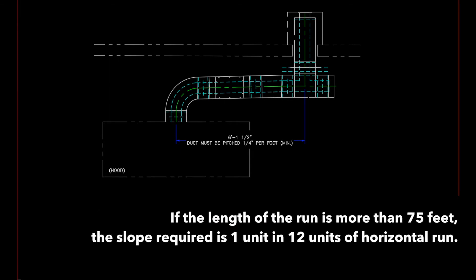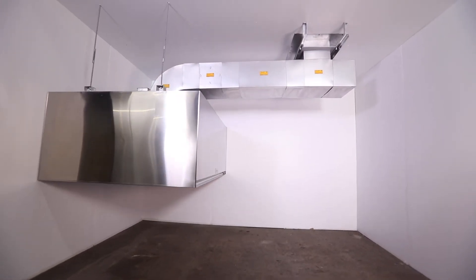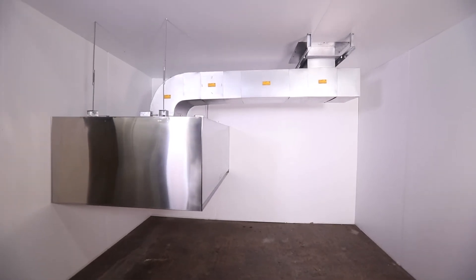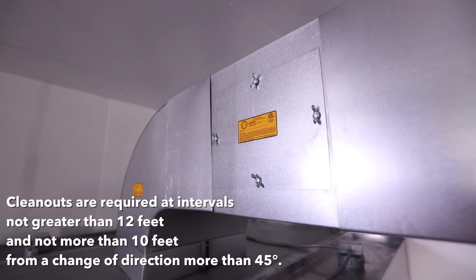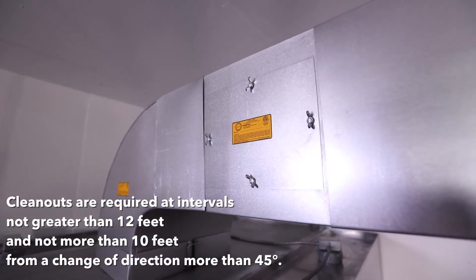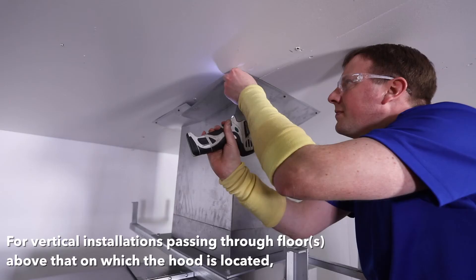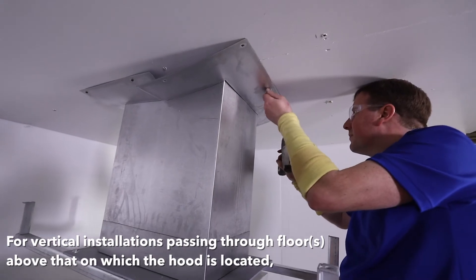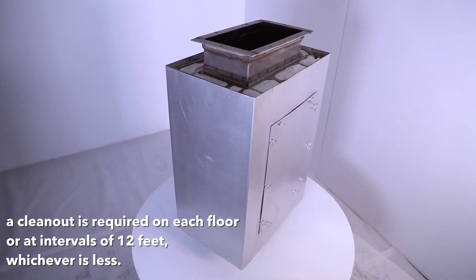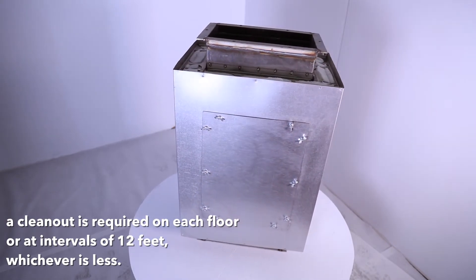If the length of the run is more than 75 feet, the slope required is one unit to 12 units of horizontal run. Third, for horizontal runs where personnel entry is not possible, cleanouts are required at intervals not greater than 12 feet and not more than 10 feet from a change of direction more than 45 degrees. For vertical installations passing through floors above that on which the hood is located, a cleanout is required on each floor or at intervals of 12 feet, whichever is less.